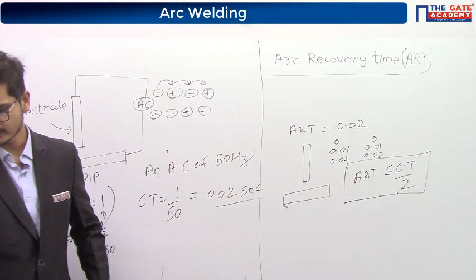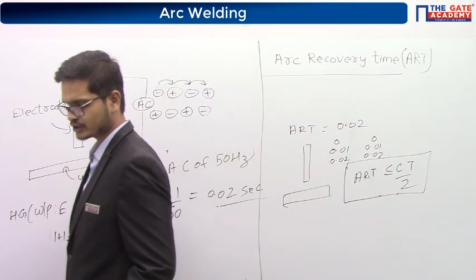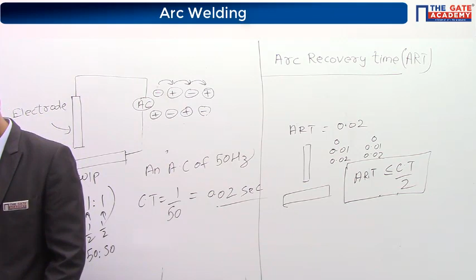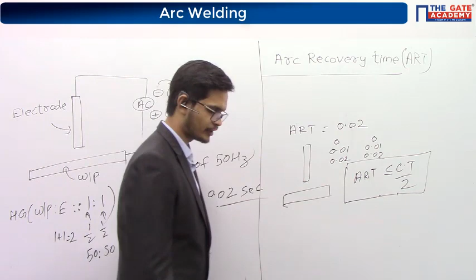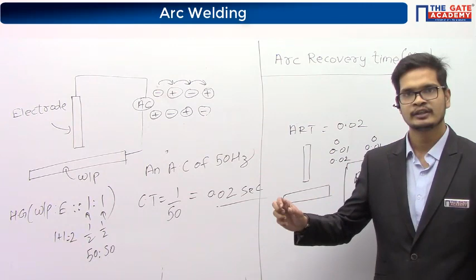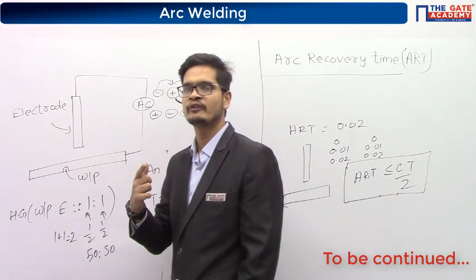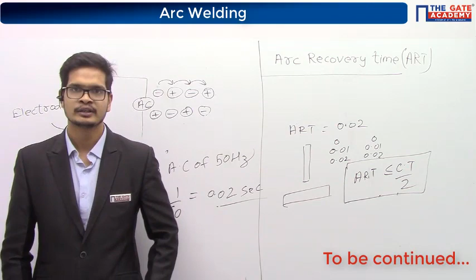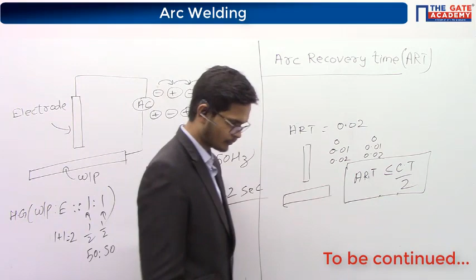Hence the minimum voltage of power supply is about 30 volts, and maximum voltage of power supply is limited to 80 volts for the safety of the welder. Minimum is limited to 30 to reduce the arc recovery time. Another thinking would be, sir, we can keep very high voltage, so arc recovery time will be minimum. But if you keep the voltage very high, there are chances that the welder may get an electric shock. There will be high potential difference, and if the potential difference is high, there are high chances of shock. Therefore, the maximum voltage is generally limited to 80 volts.